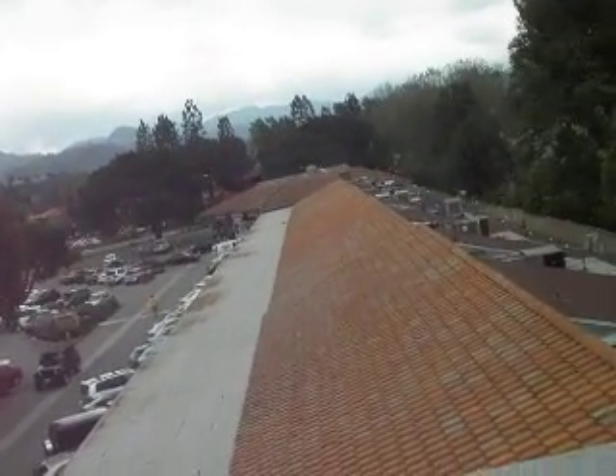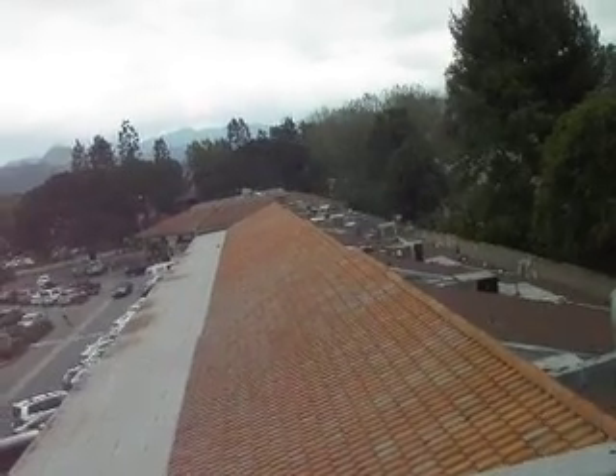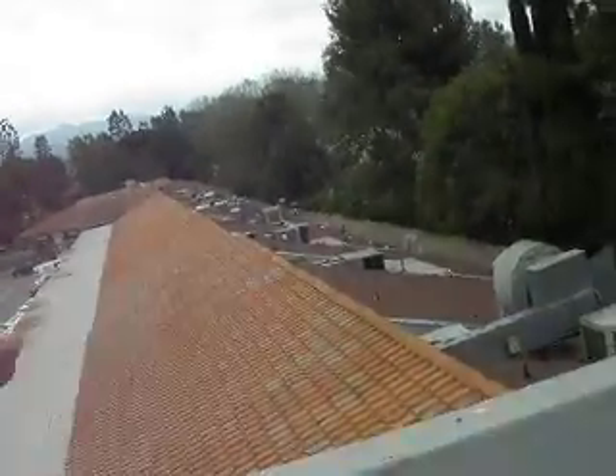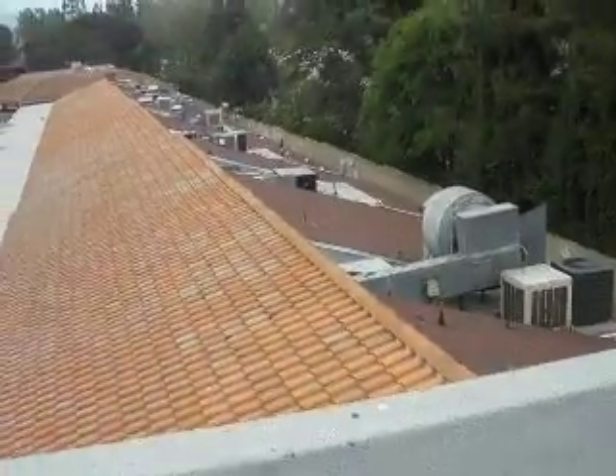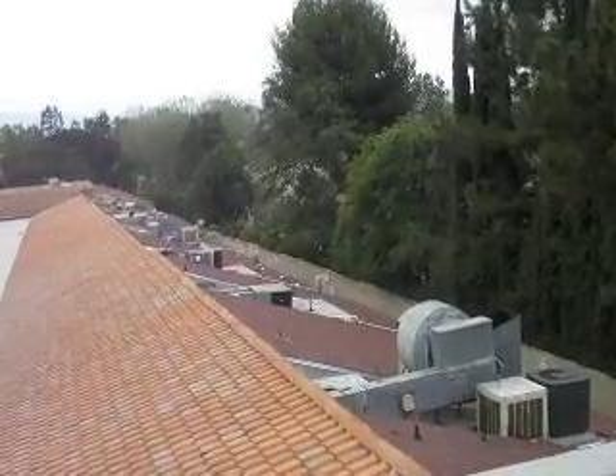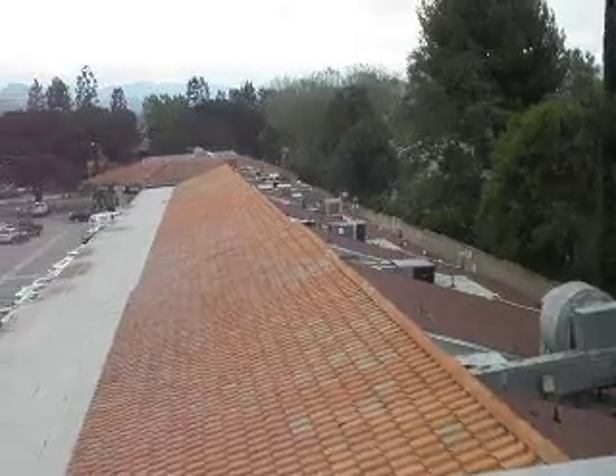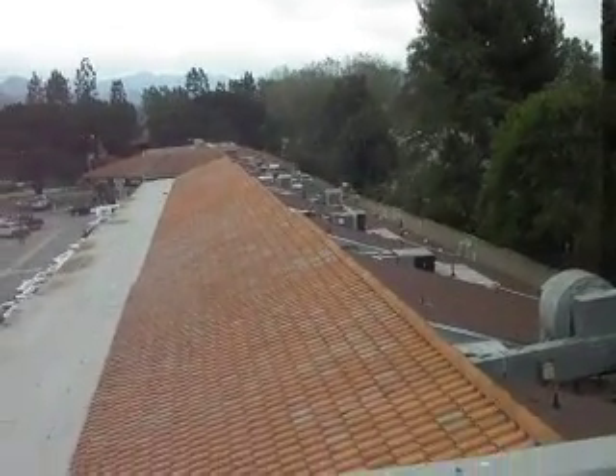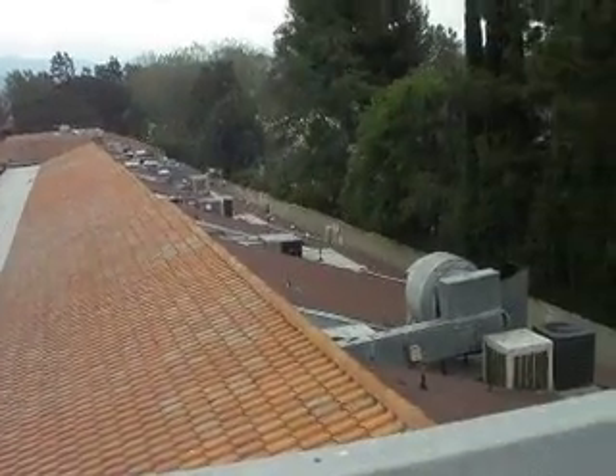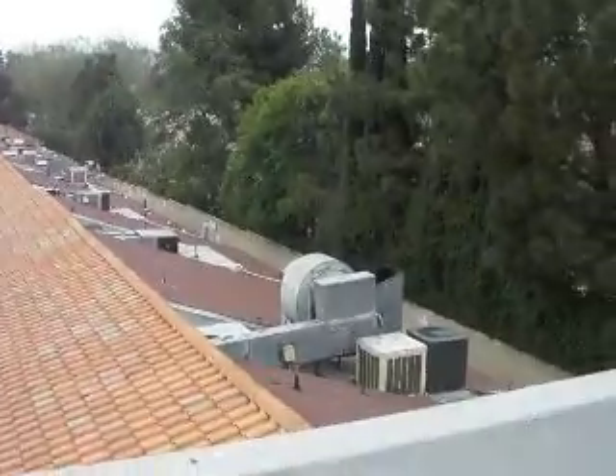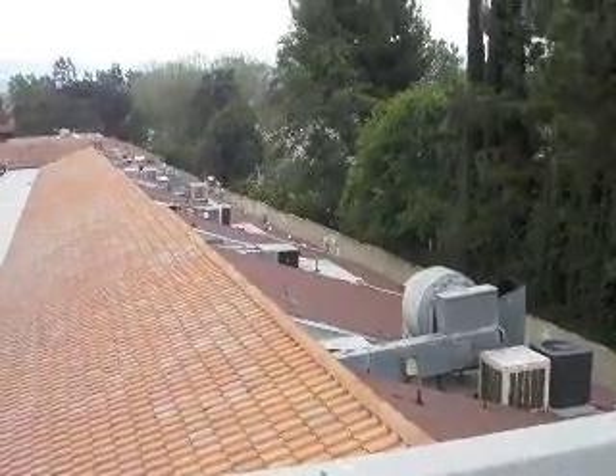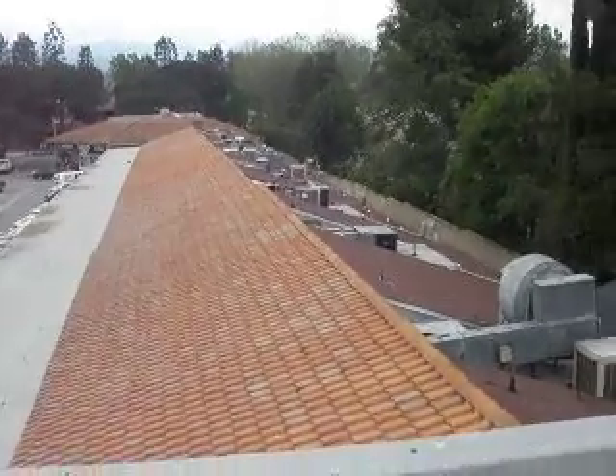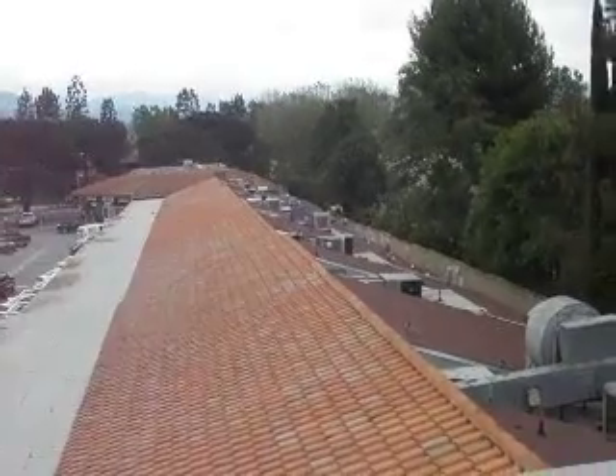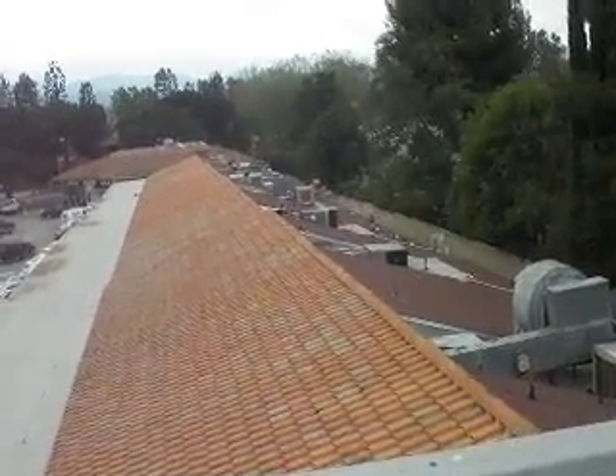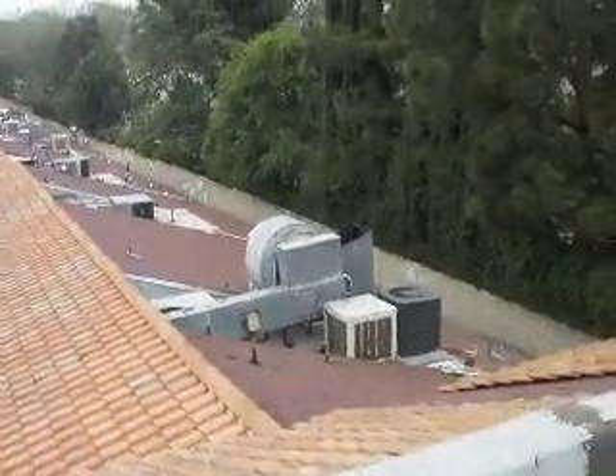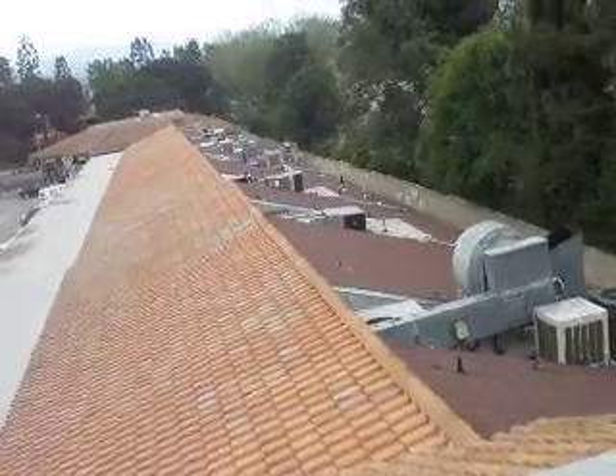And for right now, and of course the Chinese restaurant, that's a whole other nightmare. You got the 2 split systems where you got the air handlers up in the attic, and those things either leak or they get plugged up on the coils quite a bit, and those things run constantly, of course, and they got one hell of a heat load. And of course, this vent hood here sucks a lot of the air out of the restaurant. These units are trying to pump the cold air back, but in through the kitchen doors, it pulls a whole hell of a lot of air up and through there, even with the back doors open. So a lot of the cool energy is getting sucked up in through the doors and out the vent here. It needs to all be balanced.